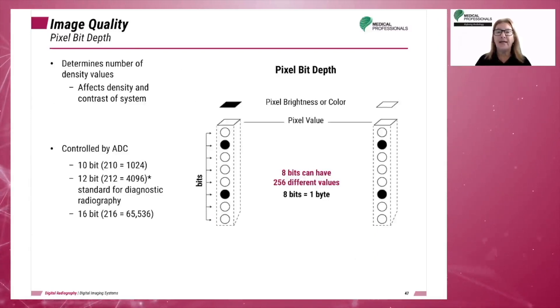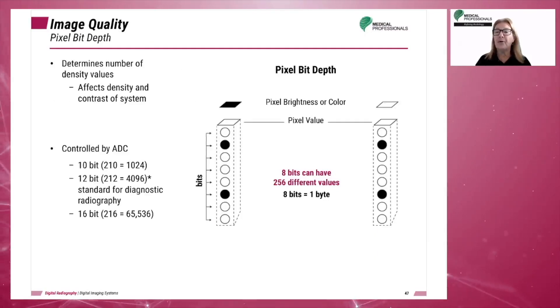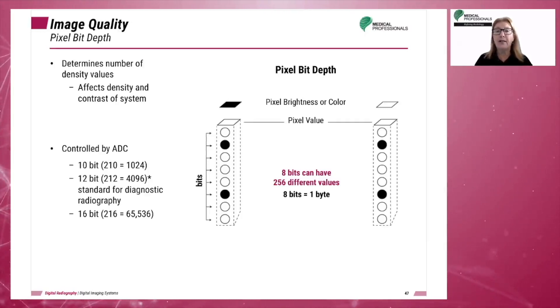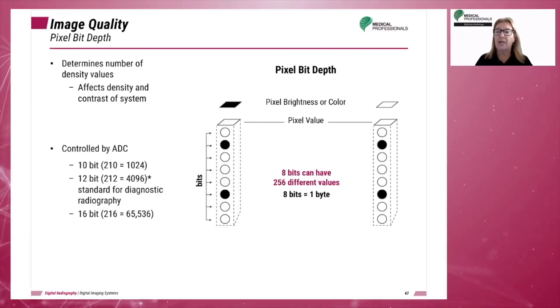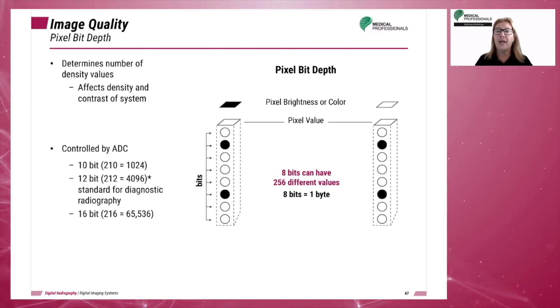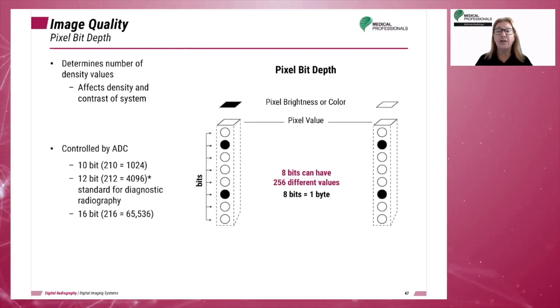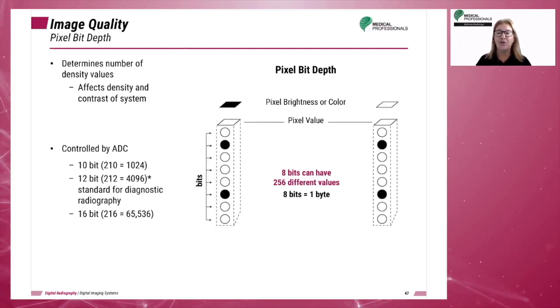Each pixel has a bit depth, or number of bits that determine the number of shades of gray each pixel is capable of recording. Pixel bit depth determines the accuracy of the digitized analog signal and the pixel brightness or gray level. Bit depth is determined by the analog to digital converter. Higher bit depth allows for a greater number of shades of gray to be displayed on the monitor and has better contrast resolution.